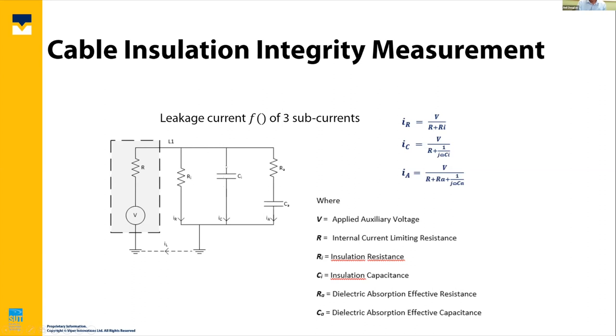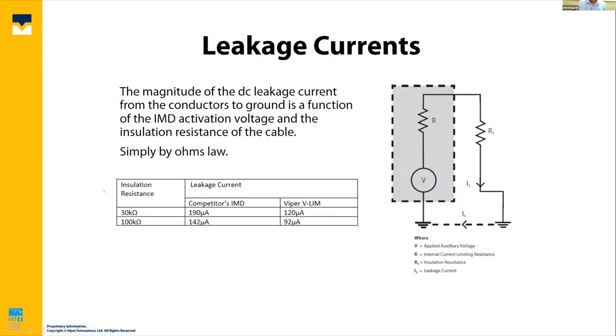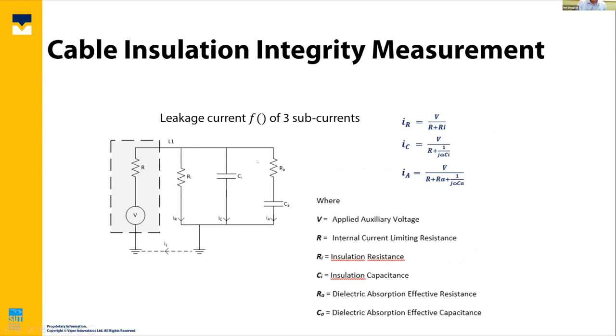And that is known as the insulation capacitance. Sorry, I should go back here. I've clicked on what I shouldn't have done. And then the final component is a little bit more complex, but that reflects the dielectric absorption element of the insulation material. So this is current that is going from the conductor through the insulation material around the cable to seawater or the armor of the cable.